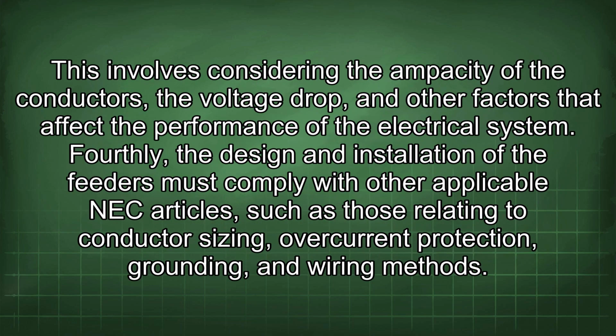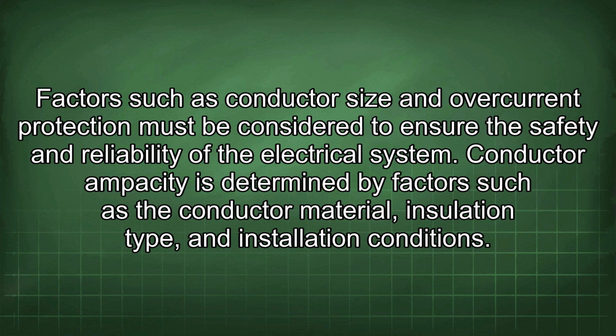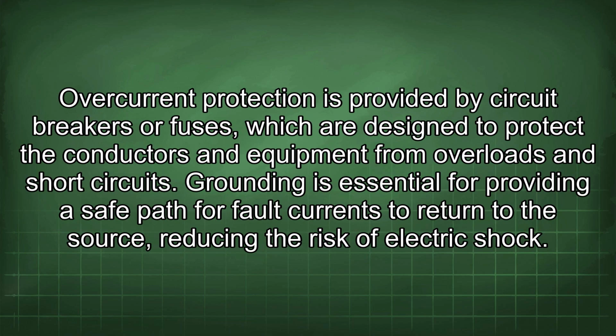This involves considering the ampacity of the conductors, the voltage drop, and other factors that affect the performance of the electrical system. Fourthly, the design and installation of the feeders must comply with other applicable NEC articles, such as those relating to conductor sizing, overcurrent protection, grounding, and wiring methods. Factors such as conductor size and overcurrent protection must be considered to ensure the safety and reliability of the electrical system. Conductor ampacity is determined by factors such as the conductor material, insulation type, and installation conditions. Overcurrent protection is provided by circuit breakers or fuses, which are designed to protect the conductors and equipment from overloads and short circuits. Grounding is essential for providing a safe path for fault currents to return to the source, reducing the risk of electric shock.